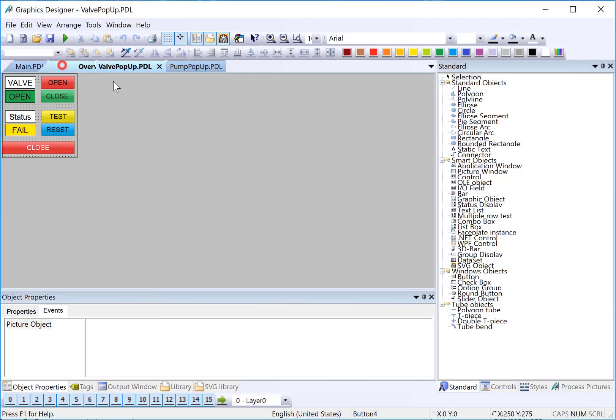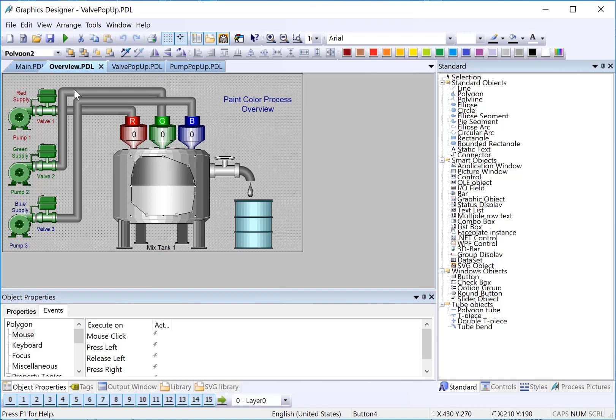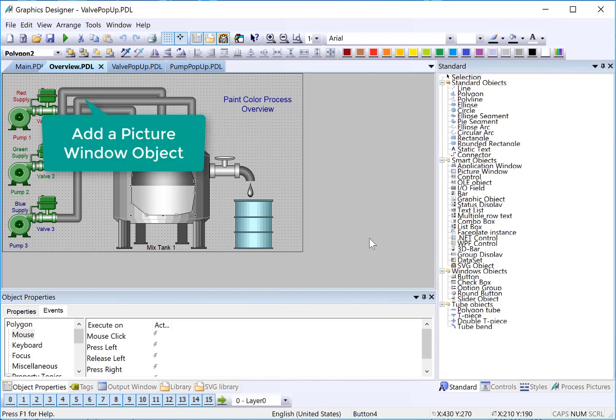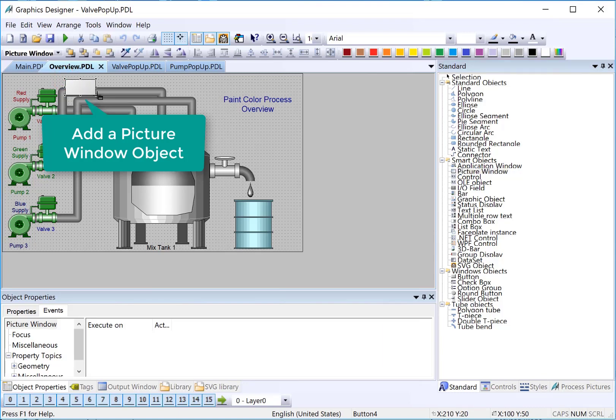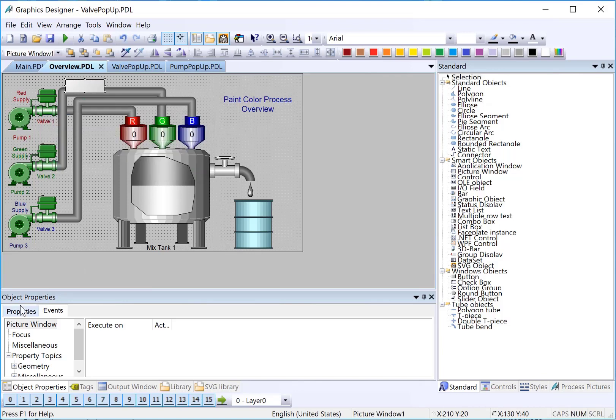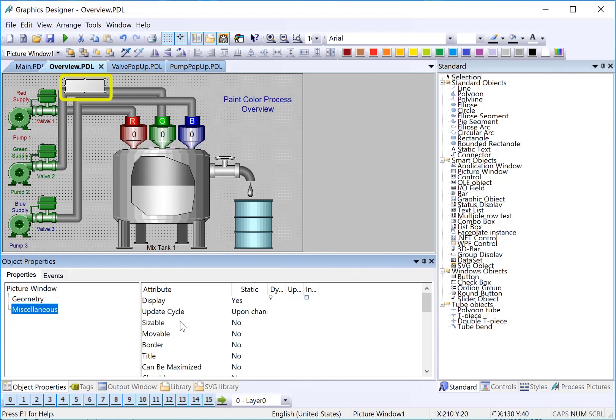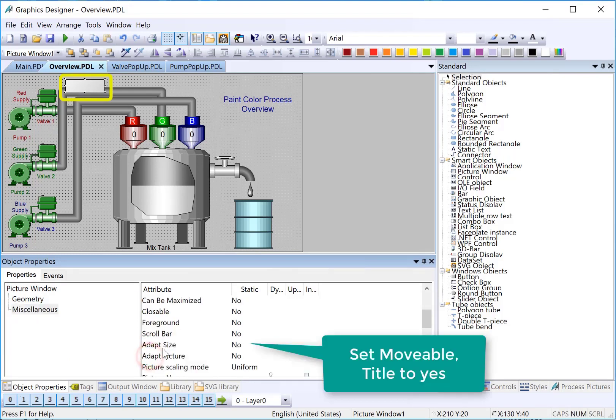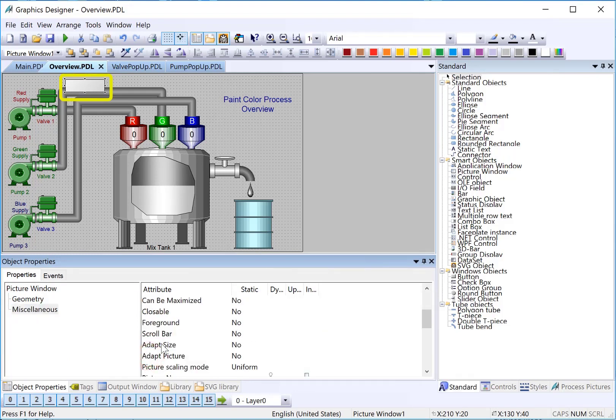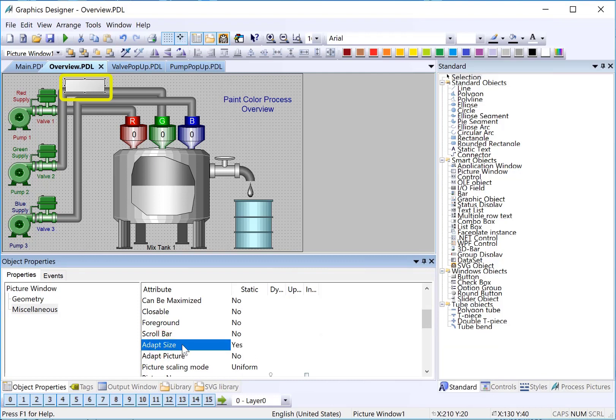Now, we're going to go to the overview screen. And we're going to use picture windows to add these pop-ups for our pumps and valves. I'll choose picture window and I will just put it here. I'm not going to worry too much about sizing it because we're going to adapt it. So, I will drop the picture window. And then on the properties dialog, I am going to set my movable and my title. And I will do adapt size. Adapt size will make the picture window grow to accommodate whatever picture you show in it.